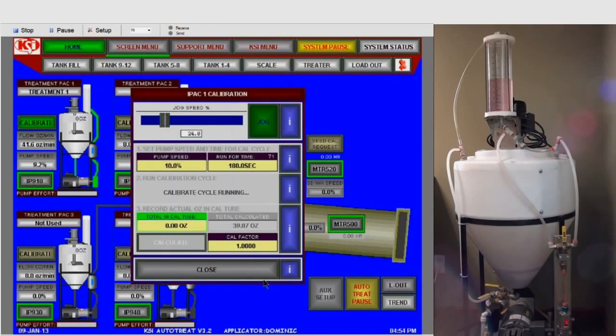The other thing I will point out is we are currently calibrating a flow meter. There are some sites that use a scale and control that pump off of loss-in-weight from a scale instead of through a flow meter. There is still a calibration process required for that loss-in-weight system. We're not calibrating the flow meter anymore, we're figuring the density on the liquid. But the calibration process that you will go through will be exactly the same as this, and you will be trained specifically on the system that you have. So again, the process is exactly the same, whether you have a flow meter or a scale, but we still do have to run it multiple times a day to ensure accuracy of the system.